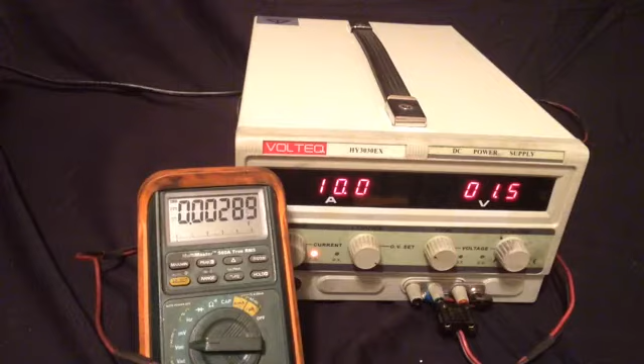Now, somebody brought up the point that how can you measure something so precisely? I mean, look at the voltmeter. It's wandering all over the place. Well, that's because the probes are open and I'm touching them. But if I put these probes on the job, immediately the voltage settles down and it becomes very repeatable, very accurate, and stable. This test setup is useful for measuring lots of other things, not just armatures.